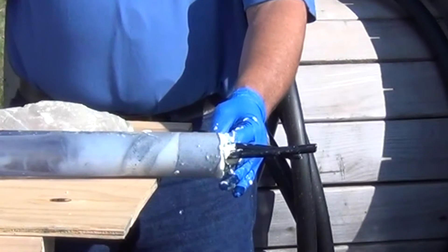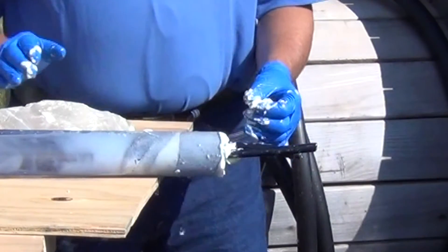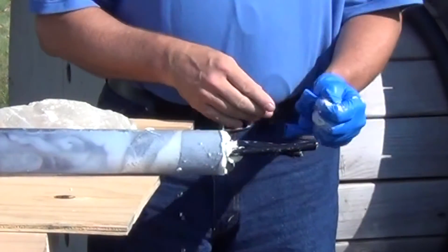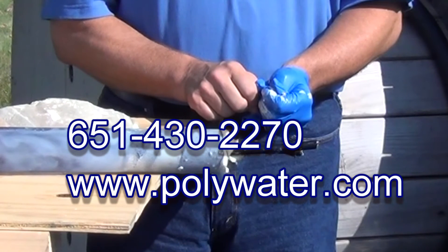The FST will expand in two to five minutes, and you can release the seal at that time. In 10 to 15 minutes the foam will be hard. The seal is now complete — it will hold up to 90 feet of water head. To order, contact American Poly Water.